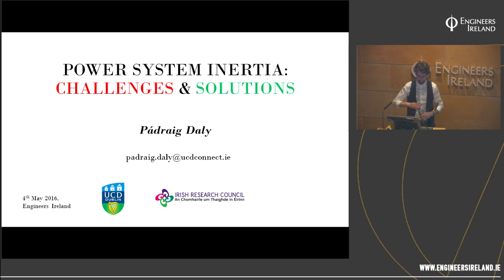Well, take the latter part first. An HVDC link has power electronics on either end. It has a converter, just like PV and wind turbines, so you can control that to provide ancillary services to the grid. Just like an offshore wind farm has a converter station onshore and you can control the voltage with that, same with a DC link. We currently have reserve coming from both our interconnectors in the case of a contingency on the grid, so they're already providing stability services to the power system. I wouldn't build a cable to provide ancillary services given the cost of it, but what it can provide is roughly the same as an offshore wind farm or onshore wind farm for that matter.